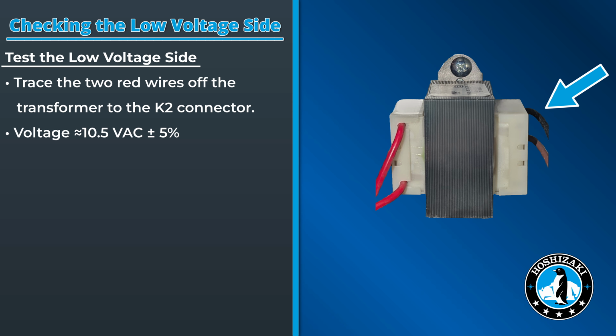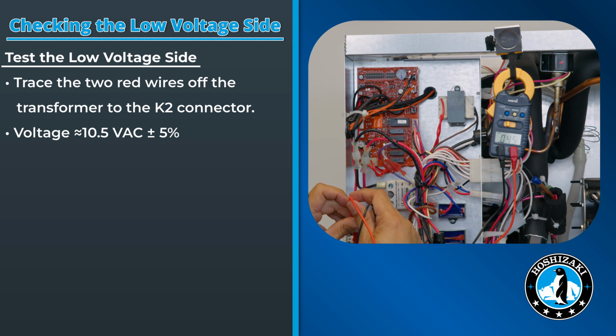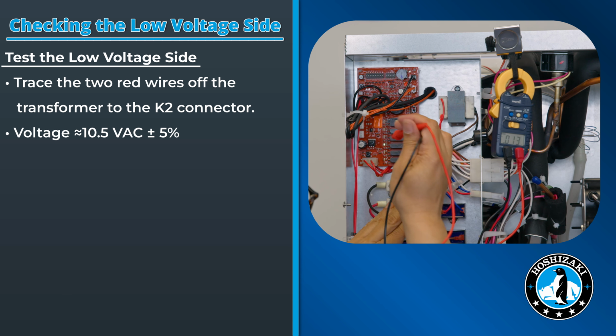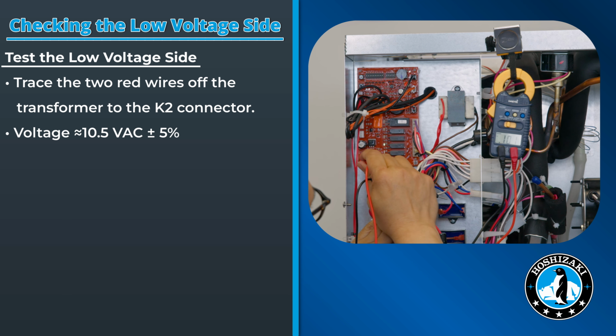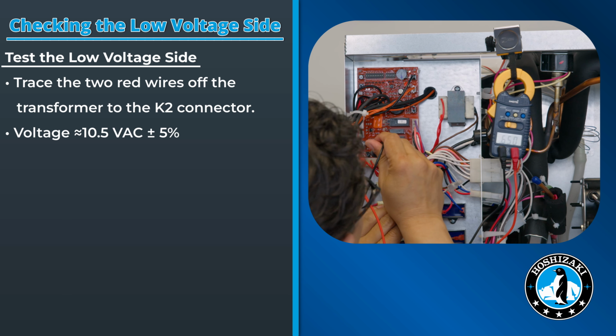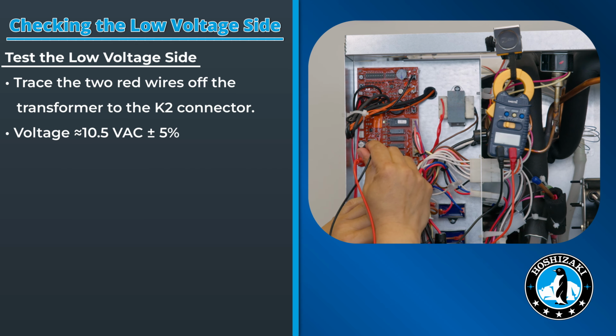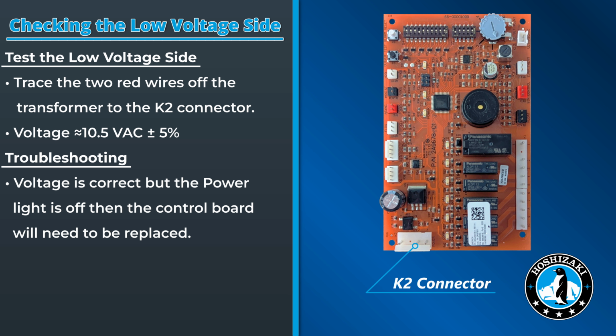Now that we confirm the proper voltage going into the control transformer, we will verify the low voltage output coming from the transformer. Trace the 2 red wires leading to the K2 connector at the control board. Measure the voltage between them. The reading at the K2 connector should be 10.5 volts plus or minus 5%. If the control voltage is present at the K2 connector but the power OK light is not illuminated, the control board needs to be replaced.